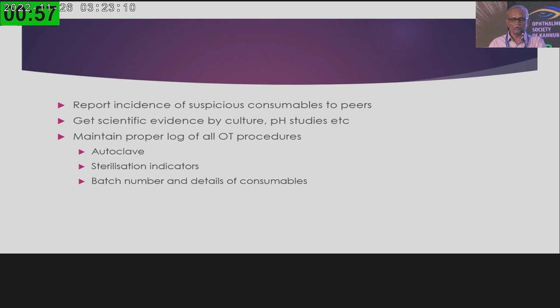Maintain a proper log of all OT procedures, including the autoclave procedure — you need not always get a printout. Even with an ordinary autoclave, you can maintain a log recording when you started, the temperature, and the holding time, all recorded in a book. All sterilization indicators must be kept and documented properly. The batch number and details of all consumables should be recorded and maintained in your OT register.